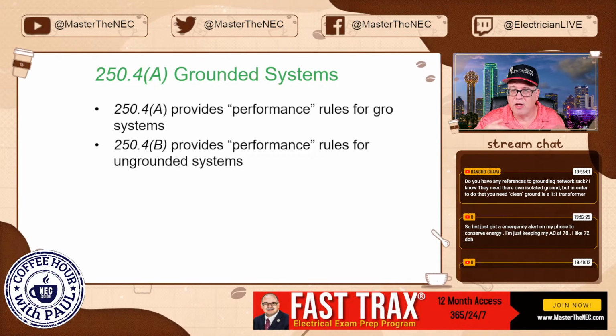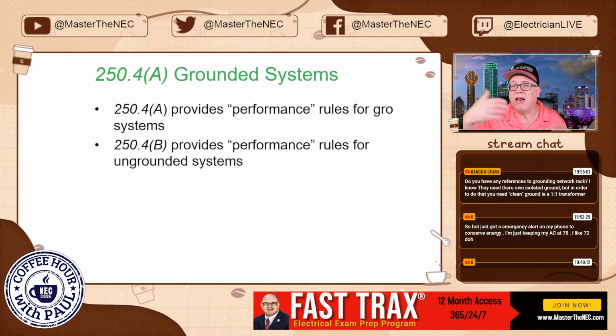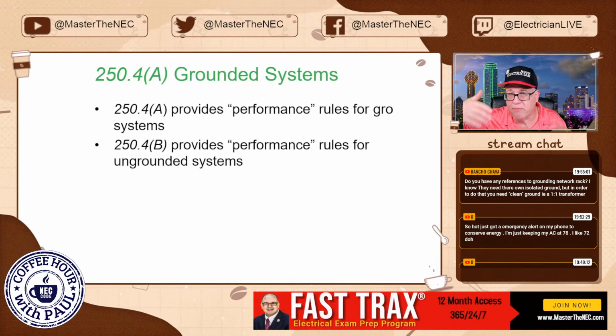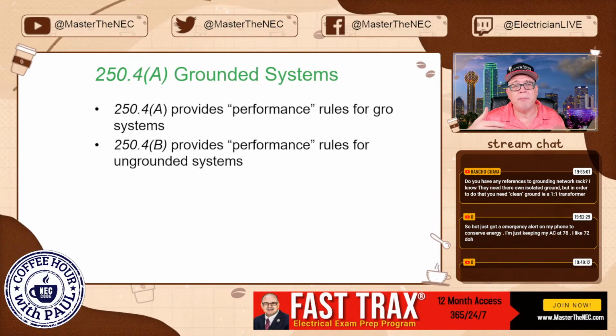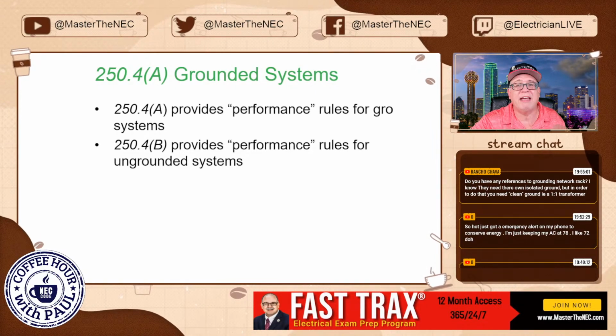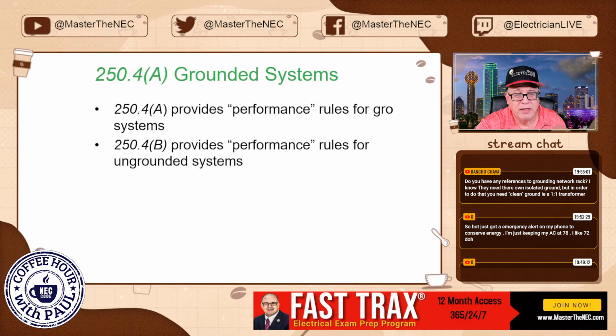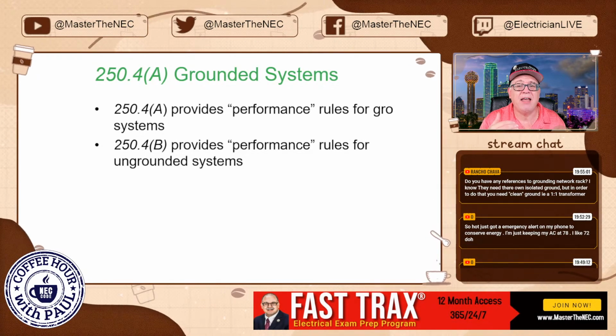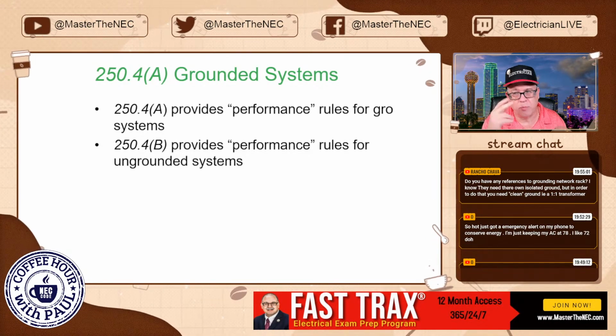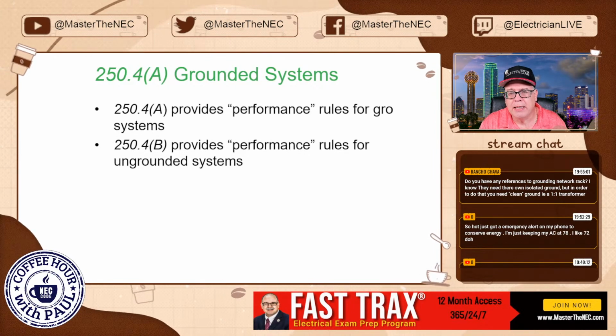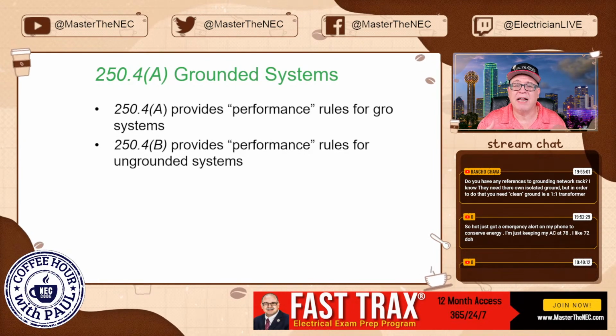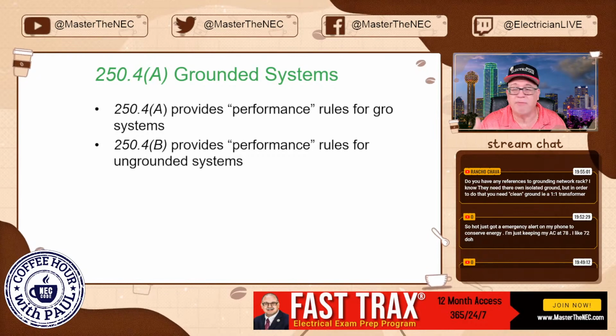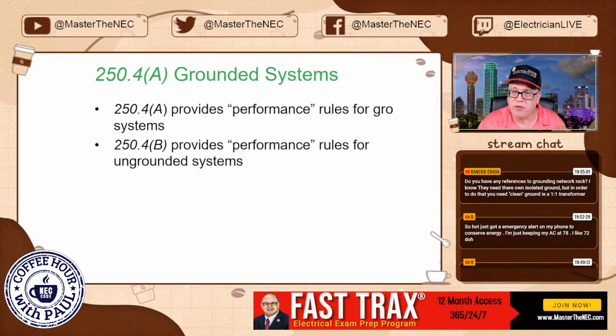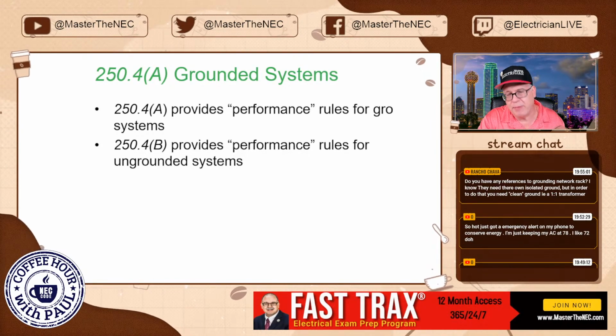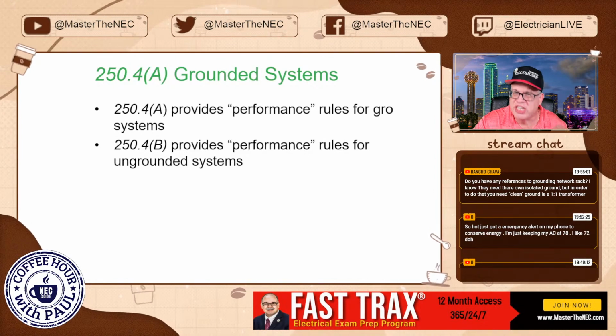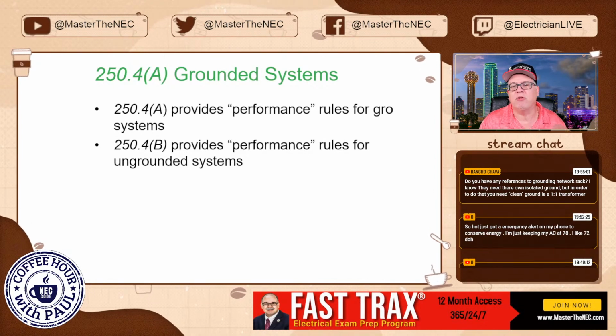250.4(A) is the performance. By following Article 250's prescriptive requirements, you're going to meet the performance, what we expect you to achieve in 250.4(A) when it comes to grounded systems, which is probably what most of y'all deal with. But again, we have rules for ungrounded systems, and if you follow those prescriptive rules, then you will meet the performance, what we expect to achieve, okay, in 250.4(B).